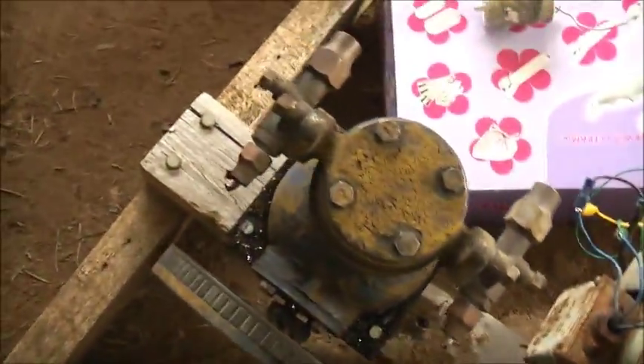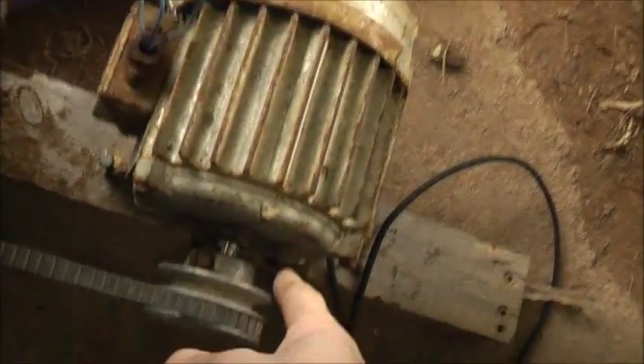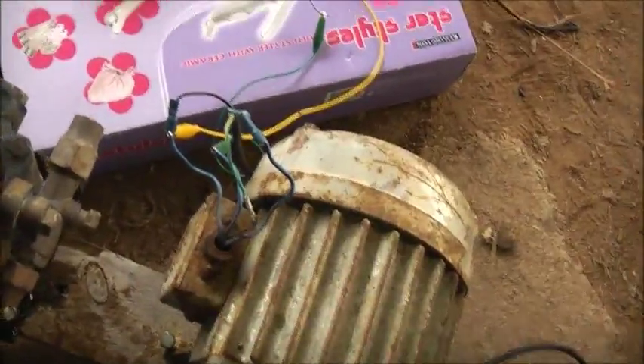It's going to take a while to get the kickstart up, but it'll work. For something like this there's not enough power — I'm going to have to try and jumpstart it a bit. But it does work. Unloaded, this sort of set up with a capacitor on single phase on a three phase motor — unloaded it's perfect for test purposes. But if you want to load them up, you've got to run them properly.